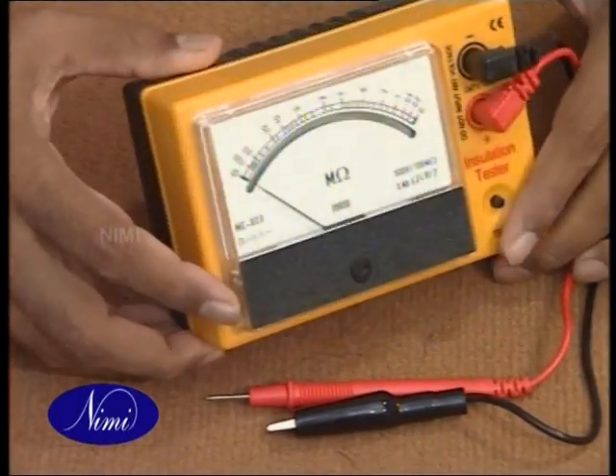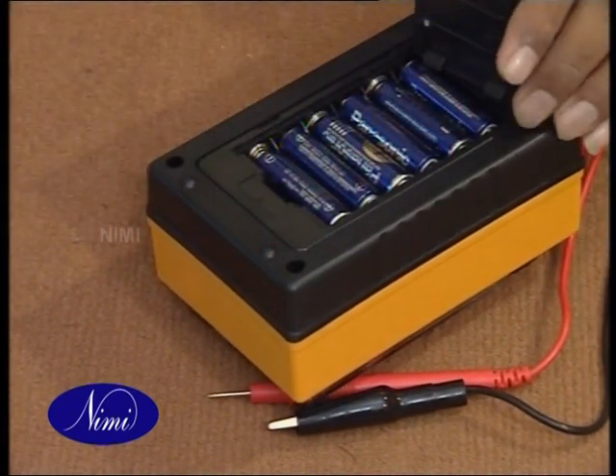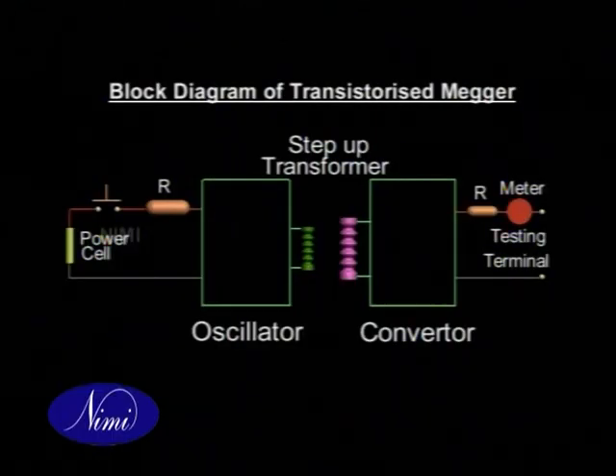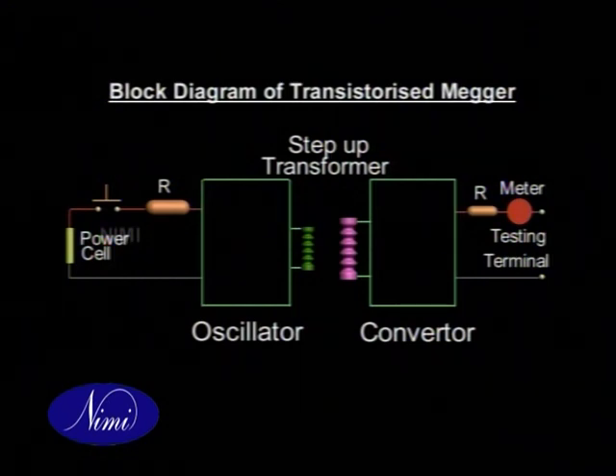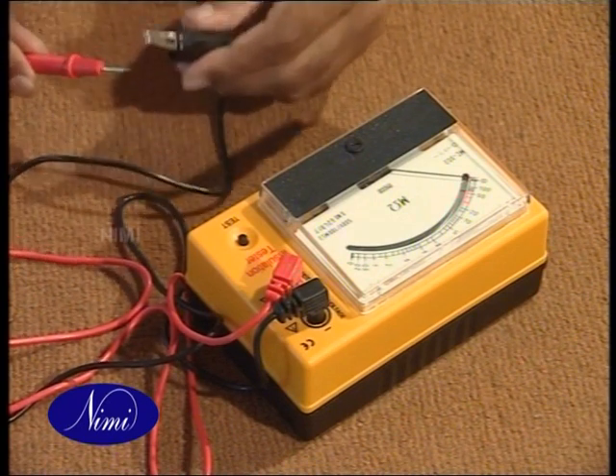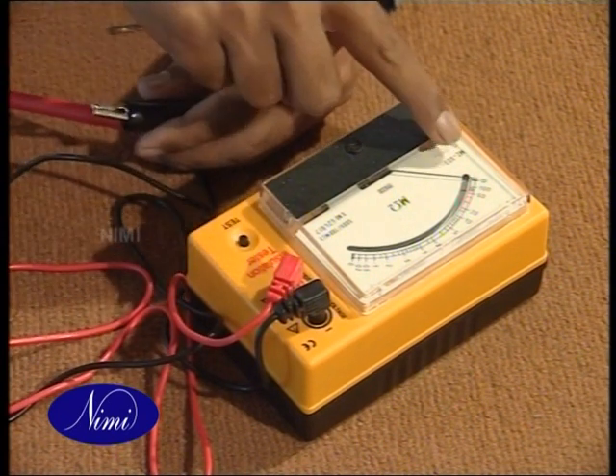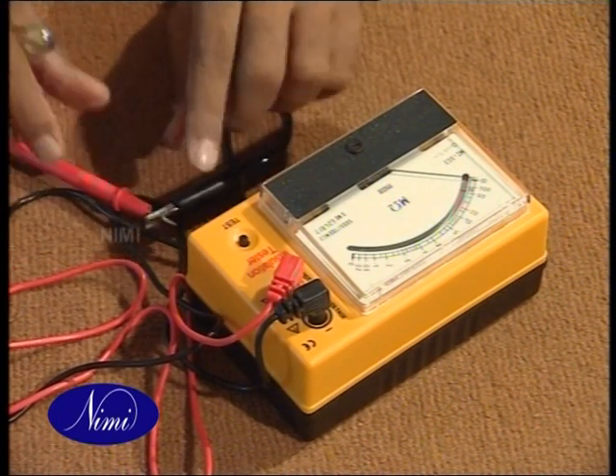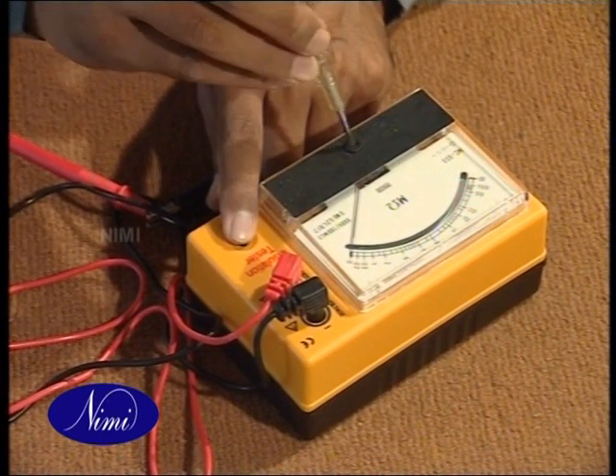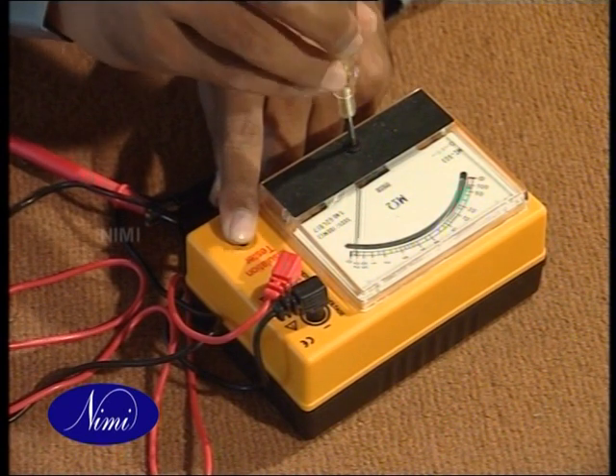A transistorized megger is an electronic insulation tester. It converts low DC voltage from a dry cell to high DC voltage by using an oscillator, step-up transformer, and a converter. The voltage generated at the test terminals is in the order of 250, 500, or 1,000 volts depending upon the design. A moving coil meter with a high resistance in series forms a series ohmmeter and has a dial graduated in megohms, similar to the conventional megger. Zero adjustment can be made to compensate for voltage variation as the cell discharges, by shorting the terminals and setting zero before any measurement.